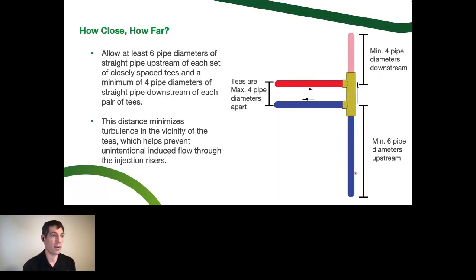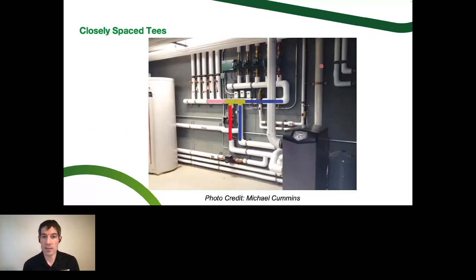So if you see primary secondary with closely spaced tees out in the field that looks like this, you're in pretty good shape. If you don't see it quite following all these rules, that would be a pretty typical thing to find out in the field, unfortunately. So it can be done, just like anything in the world, you just have to pay attention to the details, and these are a couple things that set you up to actually do closely spaced tees correctly. So this is not to scale or anything, but just to show that, and I think I even have my colors backwards here, but just to show closely spaced tees following the rules for being closely spaced, this might be just out of tolerance in this photo here.